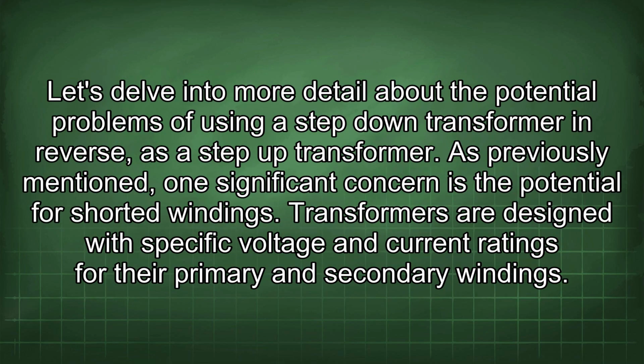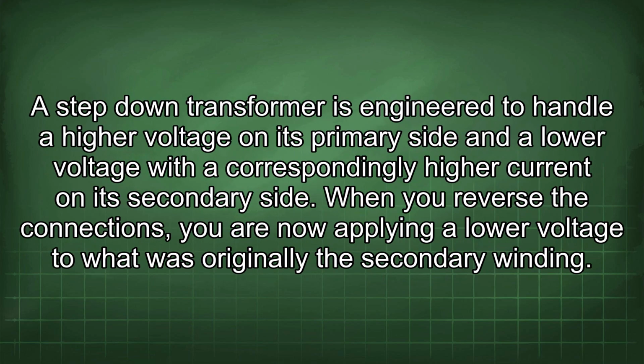Let's delve into more detail about the potential problems of using a step-down transformer in reverse as a step-up transformer. As previously mentioned, one significant concern is the potential for shorted windings. Transformers are designed with specific voltage and current ratings for their primary and secondary windings. A step-down transformer is engineered to handle a higher voltage on its primary side and a low voltage with a correspondingly high current on its secondary side.